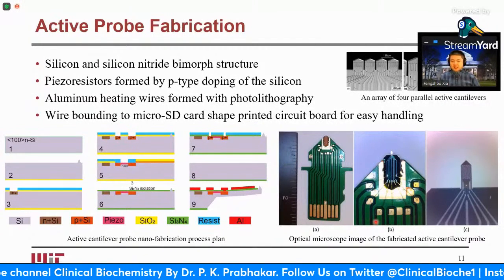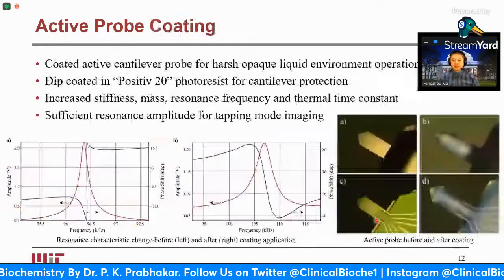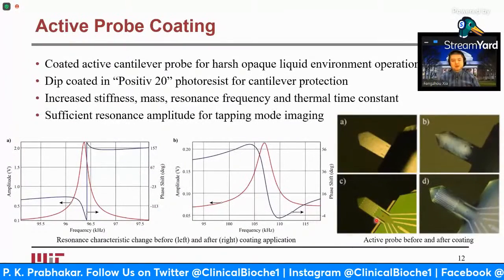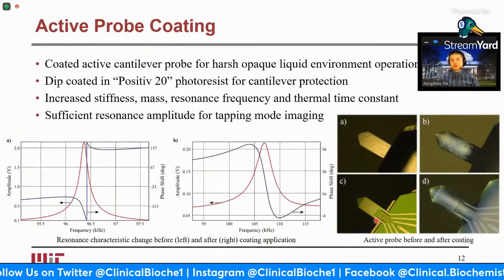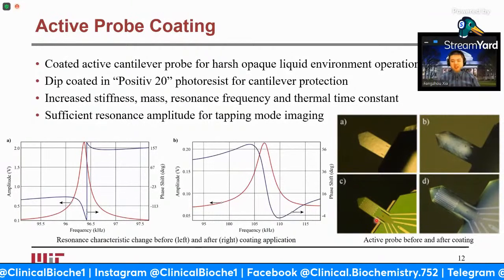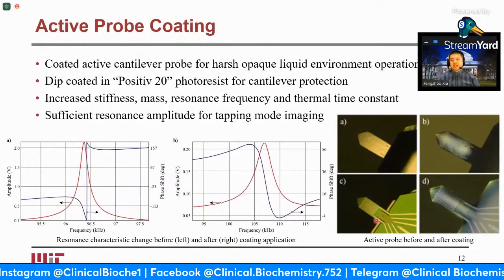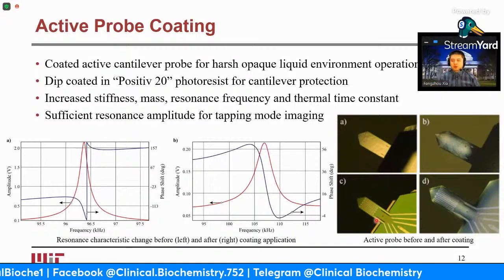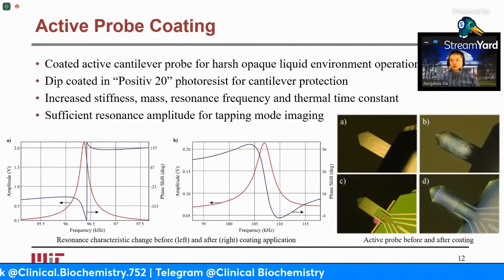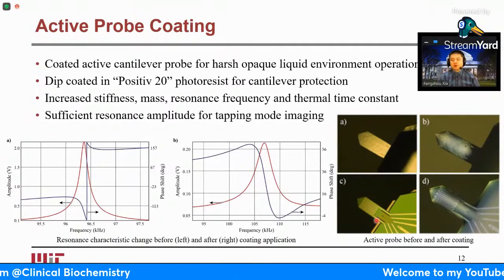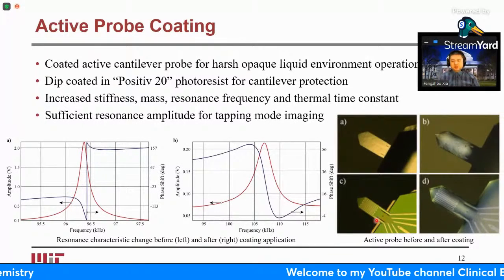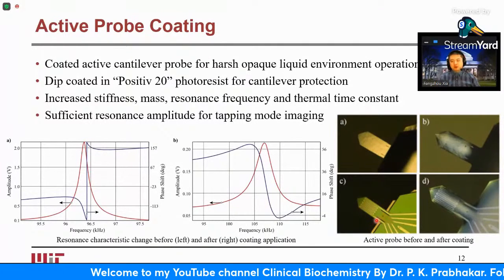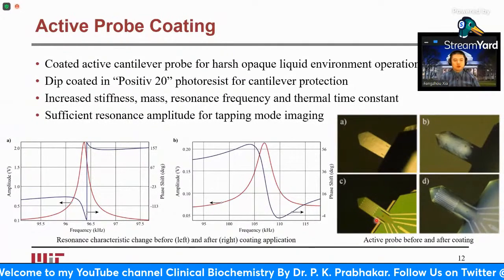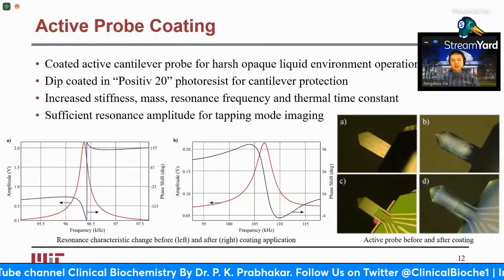One important technique that's enabled by this probe, as I have demonstrated previously in one of the publications during my PhD years, is to coat this probe with a layer of protective coating to get these active elements protected. And then it can handle chemically harsh environment. And also the benefit is, since there's no optics involved, you can do imaging of this kind of probes in opaque environment, meaning no laser path can go through there. Some example would be some raw blood sample, or as well as some crude oil, which we have done some imaging for in those areas.